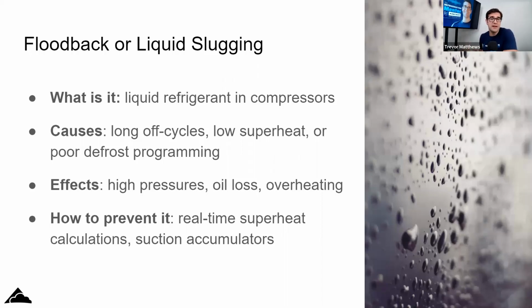In standard synthetic racks, it's still happening. It's there. A lot of the things that you can check for floodback, for example, the big one's airflow. You can measure the airflow. You can measure the oil pressure differential, because if you start to lose oil pressure differential, you could be washing it out with refrigerant. It could be something else, but it's a good sign that it could be floodback that's happening there.